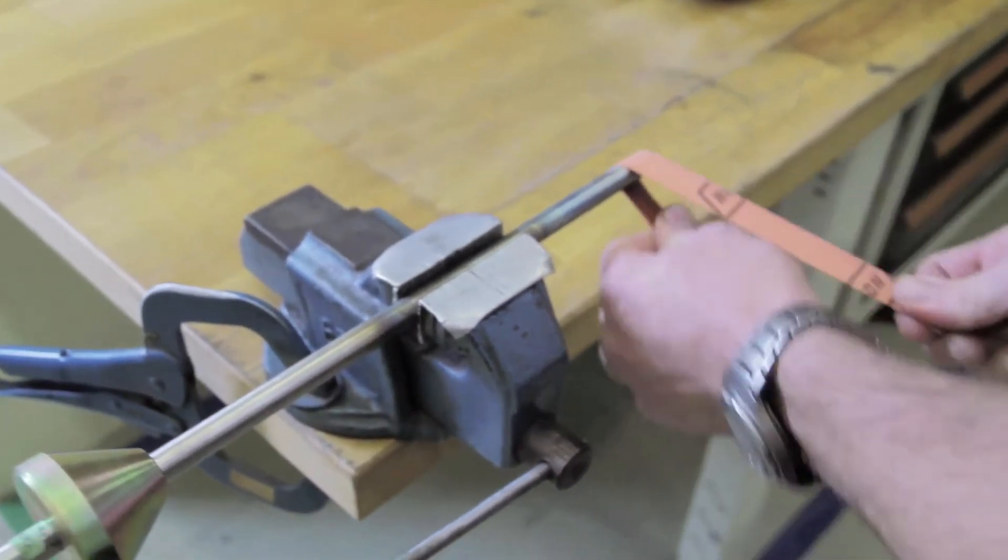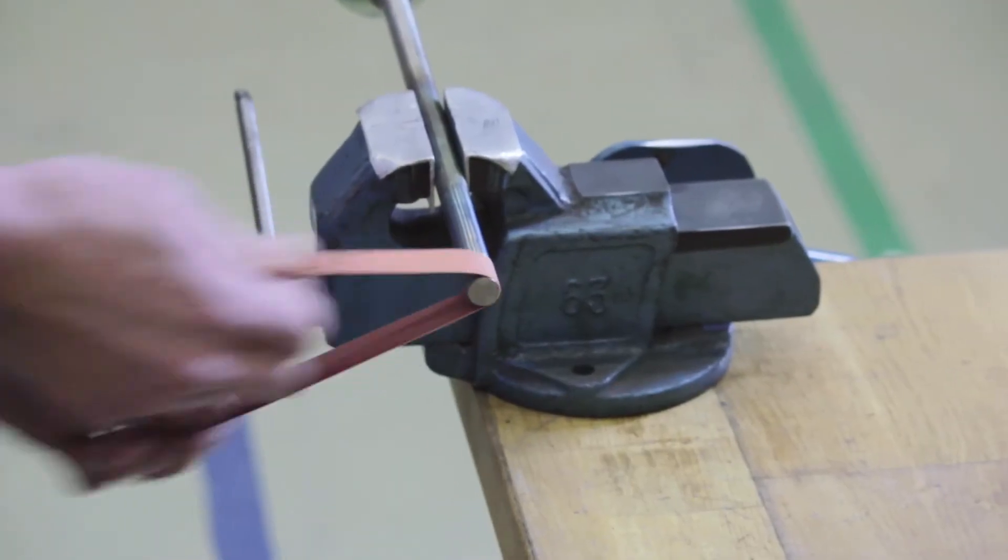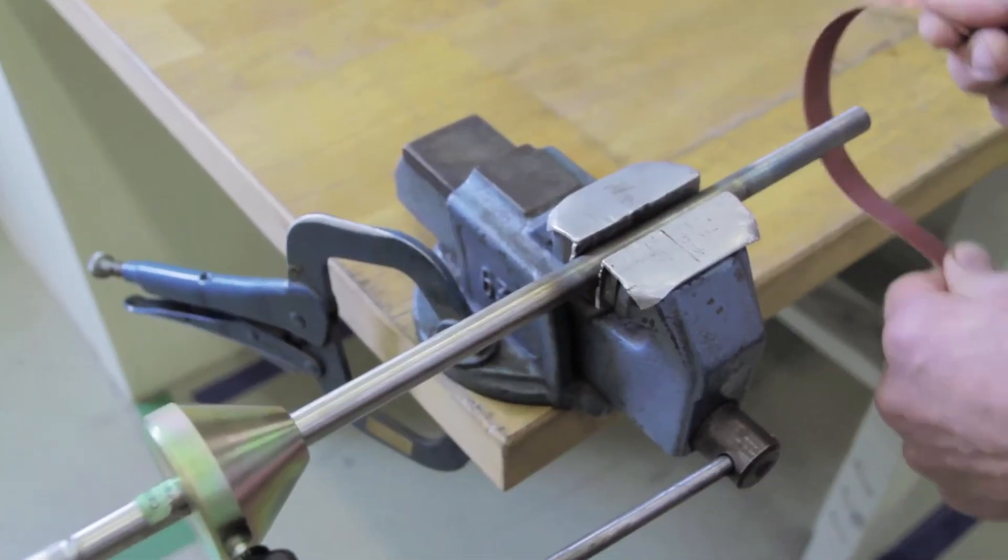Then continue with the cylindrical surface. Remove the oxide to a bit above the probe body which is 60 mm long. Take a narrow strip of emery paper and pull it back and forth until the surface is free from oxide. Repeat once.